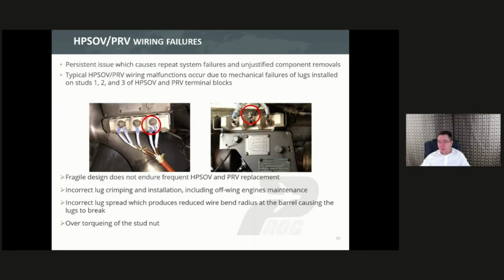Typical HPSV and PRV wiring malfunctions occur due to mechanical failures of lugs installed on studs 1, 2, and 3 of the HPSV and PRV terminals block. The fragile design doesn't endure frequent HPSV PRV replacement. Basically, it's like a snowball effect: the more components you replace, the more wiring is susceptible to damage.